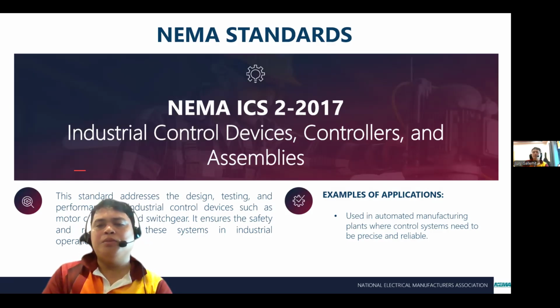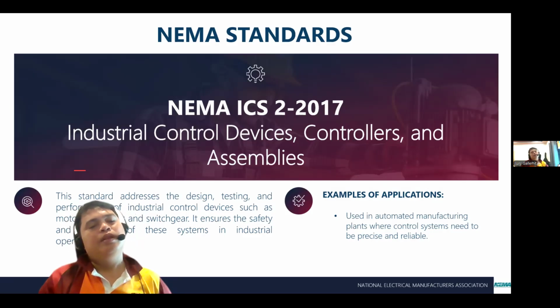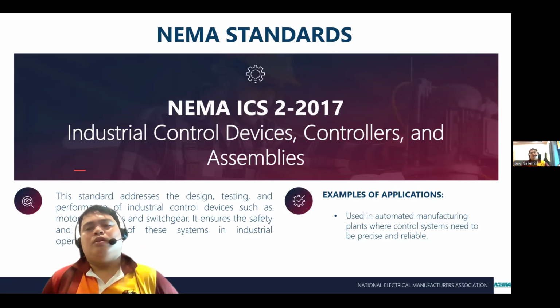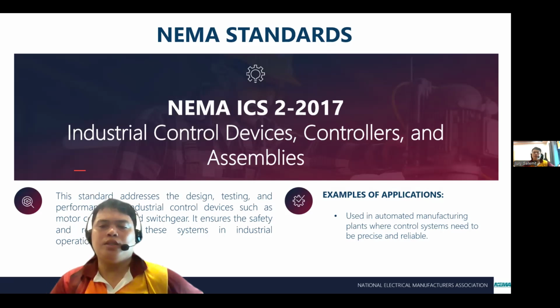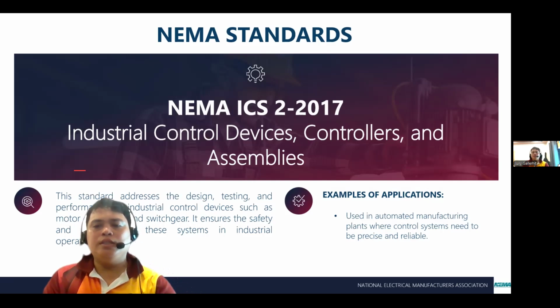These standards outline requirements for electrical ratings, mechanical durability, environmental performance, short circuit withstand capability, coil characteristics, temperature limits, and enclosure suitability. For contactors, the coil characteristics indicate the current limit, since contactors have an ampacity rating; if a contactor is too small and installed with a larger motor, it could burn out. By establishing consistent design and testing rules, NEMA helps ensure that industrial control devices operate safely, reliably, and compatibly within manufacturing, commercial, and automation environments.